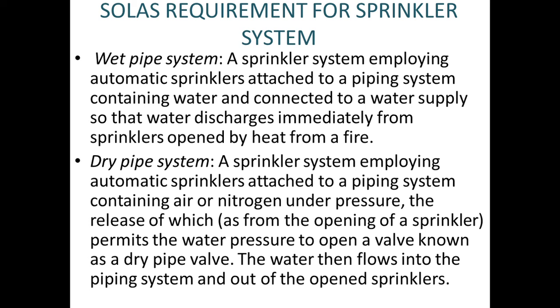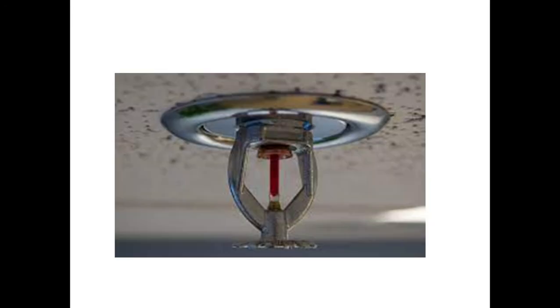Now, the dry pipe system is a sprinkler system employing automatic sprinklers attached to a piping system containing air or nitrogen under pressure. The release of this pressure, from the opening of a sprinkler, permits the water pressure to open a valve known as the dry pipe valve. Once the dry pipe valve opens, the water flows into the piping system and out of the open sprinklers. So in this dry pipe system, the piping is filled with nitrogen or air. This is the actual head we were talking about.